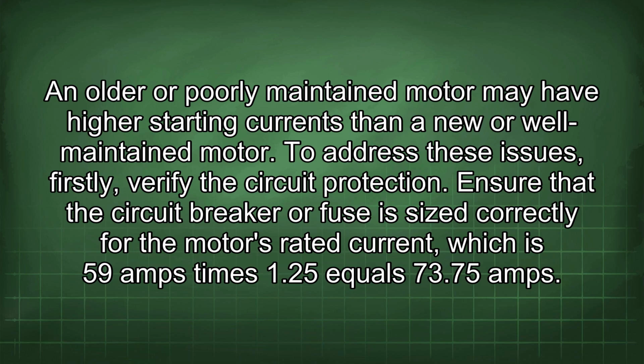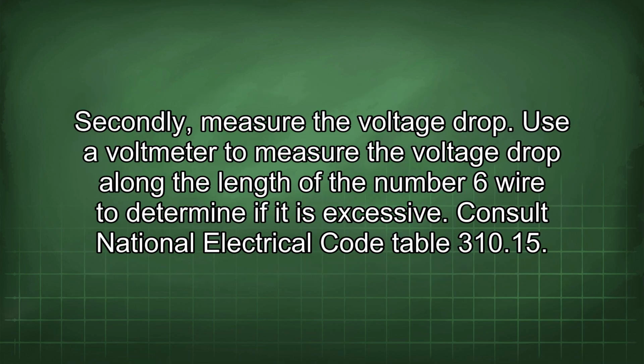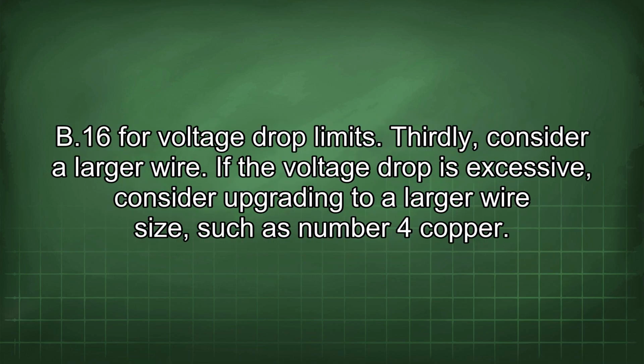To address these issues, firstly, verify the circuit protection. Ensure that the circuit breaker or fuse is sized correctly for the motor's rated current, which is 59 amps times 1.25 equals 73.75 amps. Secondly, measure the voltage drop. Use a voltmeter to measure the voltage drop along the length of the number 6 wire to determine if it is excessive. Consult National Electrical Code Table 310.15(B)(16) for voltage drop limits.